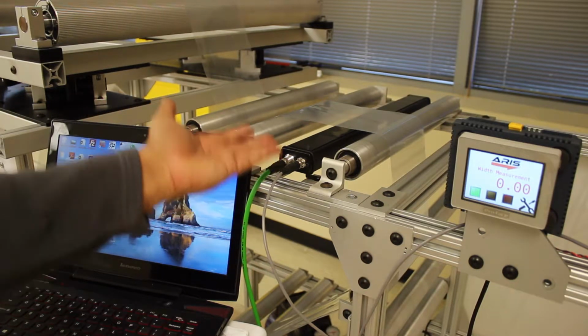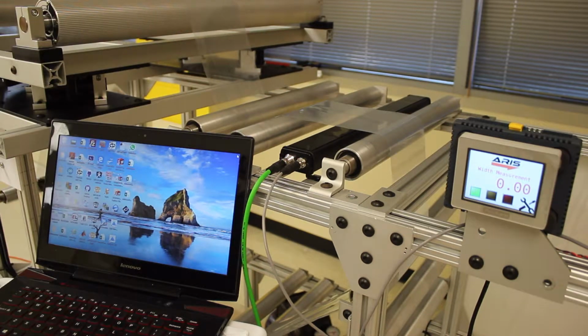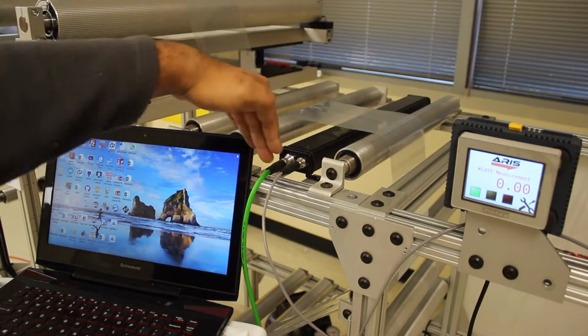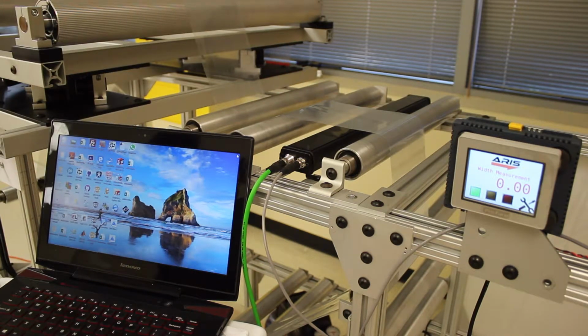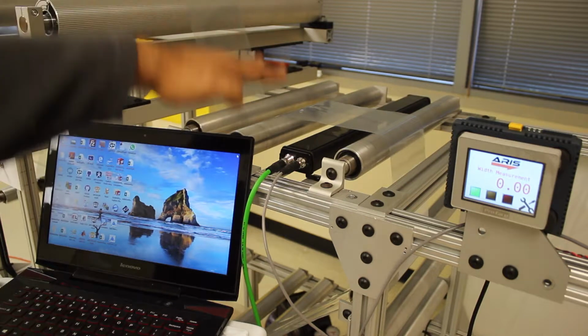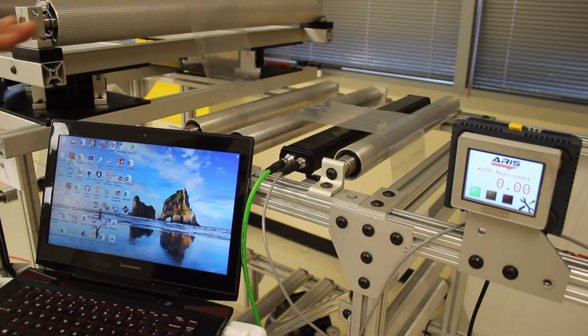The sensor is installed facing up. That is good, but just to avoid any dust and other accumulation, it may be better to face the sensor down so that it's looking down towards the web. A few other things that we need to consider is the free space behind the sensor. We want to maintain about 6 inches of free space so that nothing in the background is seen by the sensor. That's the optimal way in which we can get the best results.